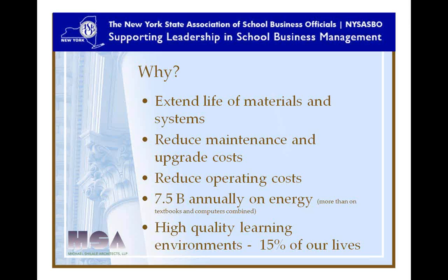And one was spending twice the fuel as the other building. And once we started benchmarking it, we figured it out, and it really had to do with the maintenance staff in one building being much better at setting the boilers back at night and closing the windows, and at the other building, the facilities director told us he didn't have that concerned a staff.